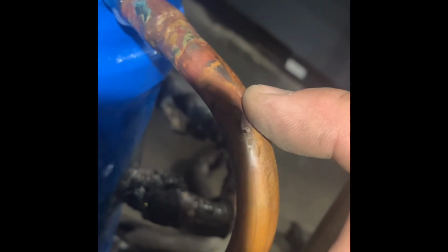It's really weird for a leak to develop right here and not up at the braze joint or something. So I'm a little wary of the integrity of the copper in this pipe. What I'm going to do is unbraze here and unbraze here, and just bend a new piece to put in there.